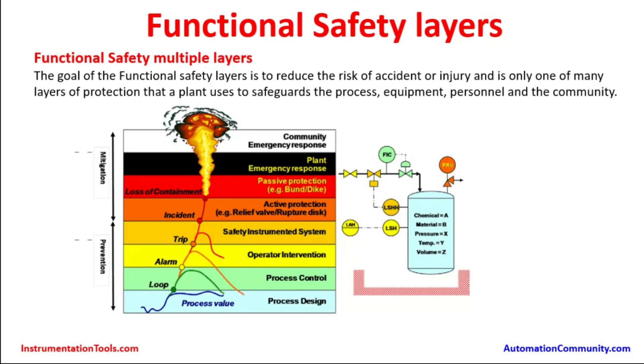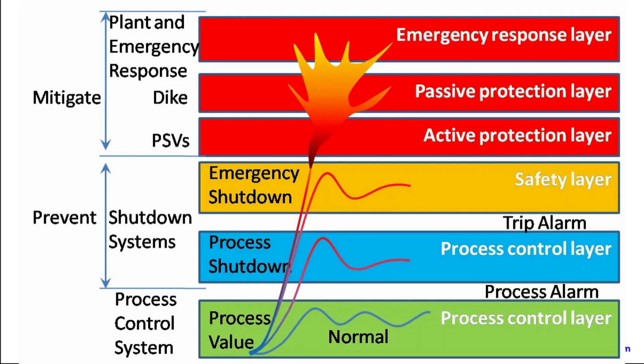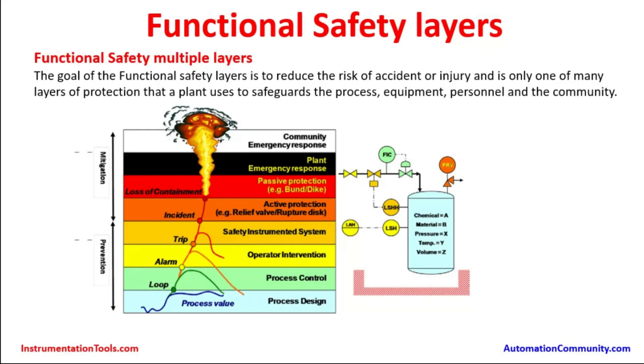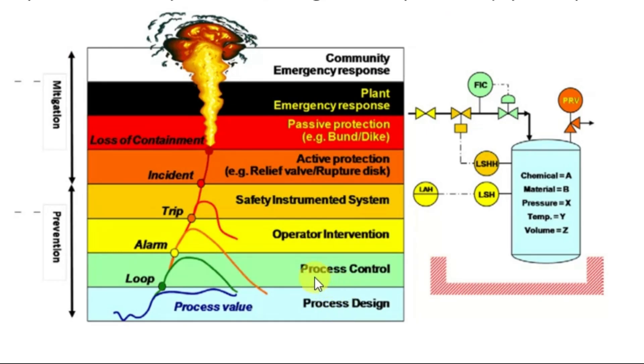Functional safety covers multiple layers. The goal of functional safety layers is to reduce the risk of accident or injury — the many layers of protection that a plant uses to safeguard the process, equipment, personnel, and the community. The different layers are shown in different colors. This is a normal process operating in steady mode. Plants are designed to operate in this steady mode. Here we have the process control — loop control and measurement — which is done by the BPCS, basic process control system, shown in green.